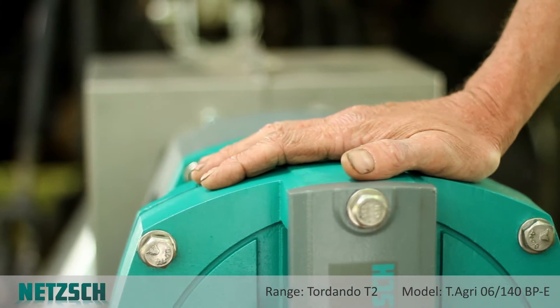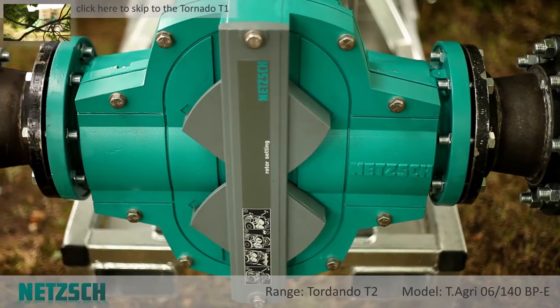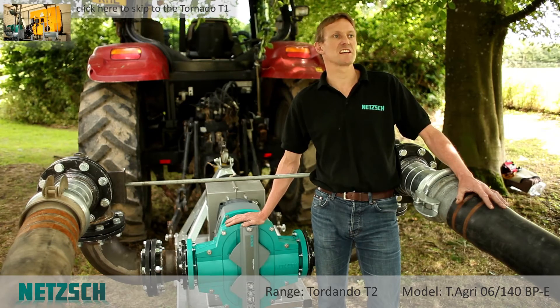This is NETZSCH rotary lobe pump from the Tornado range. The flow rate capabilities are up to 125 cubic metres per hour and up to 6 bar, capable of pumping blowable clean liquids, viscous liquids, and solids laden slurries.